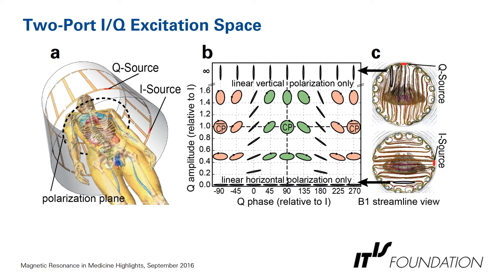The two-port IQ excitation space is illustrated here. The I and Q sources on the birdcage each result in one linear polarization: the Q source results in vertical polarization of the B1 field, and the I source in horizontal polarization. If the I and Q have the same amplitude with a 90-degree phase shift, we end up with circular polarization. If we change the relative amplitude or the relative phase, we get elliptical or linear polarizations with different polarization angles.